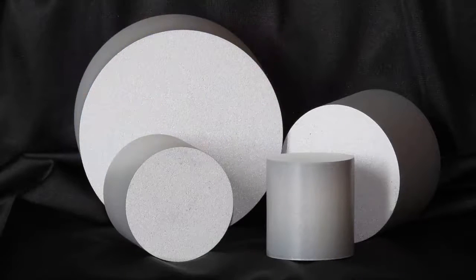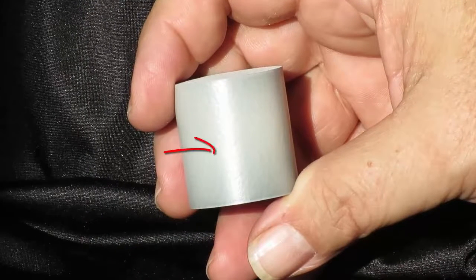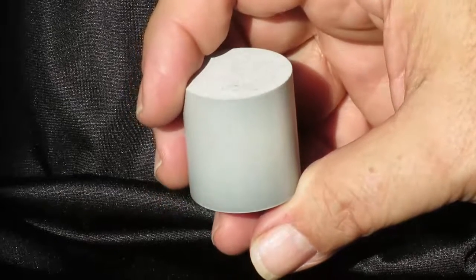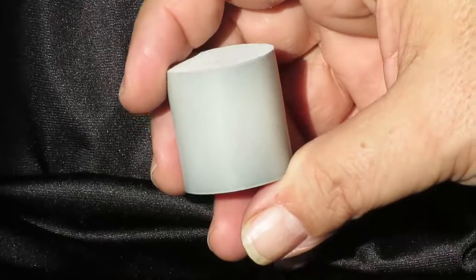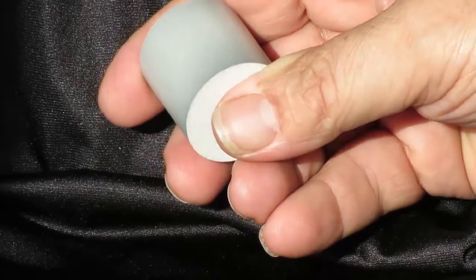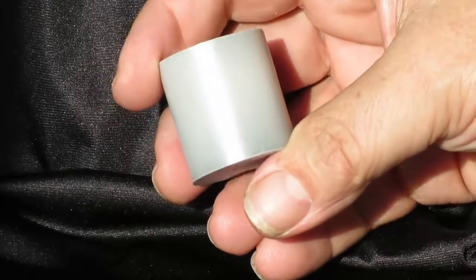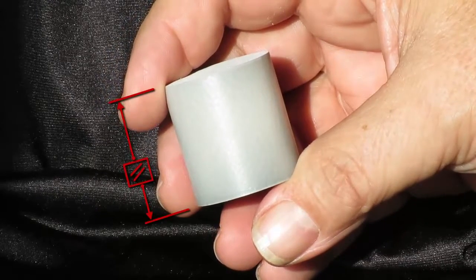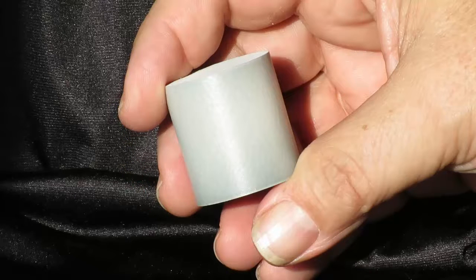Once a disc is sintered, it takes the shape of a disc we see in arrestors. Shown here is a typical distribution disc. Station class discs are much larger. On the outside surface of a disc is a layer we call the collar. It serves as an insulator and is necessary during high current surges. On the end surfaces are metal electrodes, generally a form of aluminum metal. The top and bottom must be flat and even to ensure good contact between the discs and the arrestor. All three of these aspects are of critical importance and are well controlled to ensure the quality of the disc.